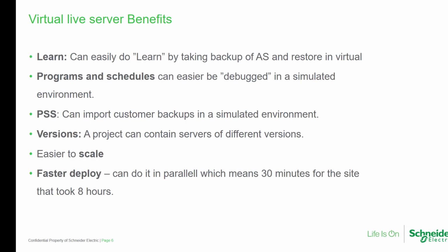So at this point, it's pretty obvious how big an advantage it is to be using the virtual live server concept. You can learn from an existing site by taking a backup of the AS and then restoring it into the PCT. You can debug your programs and schedules in a simulated environment. Product support can import customer backups into a simulated environment. You can have several different versions at the same time within a single project. It's very easy to scale, and it's much, much faster to deploy than it was within the old project configuration server.